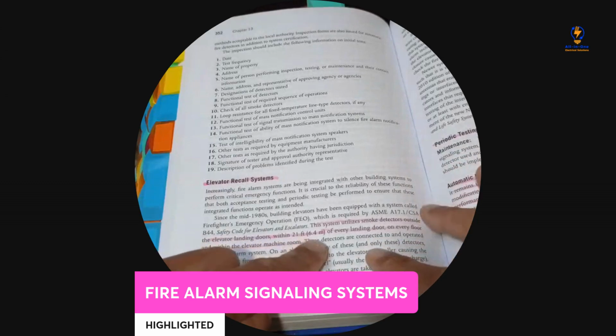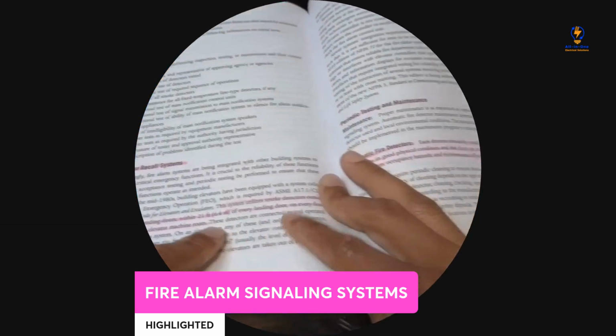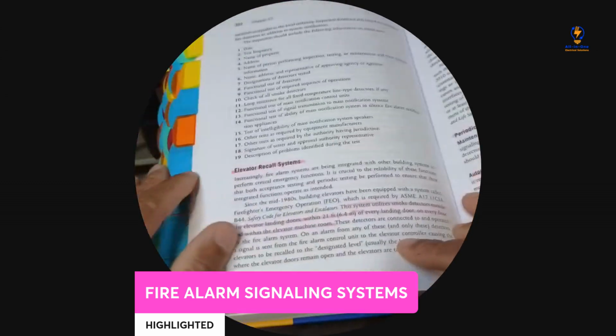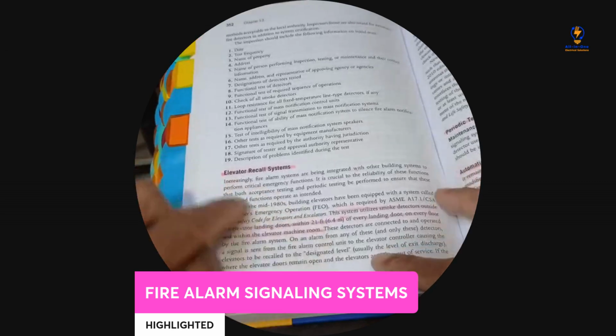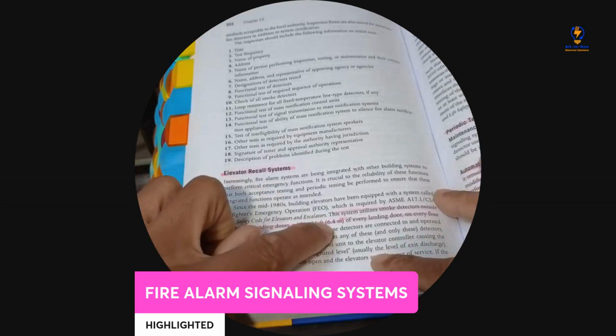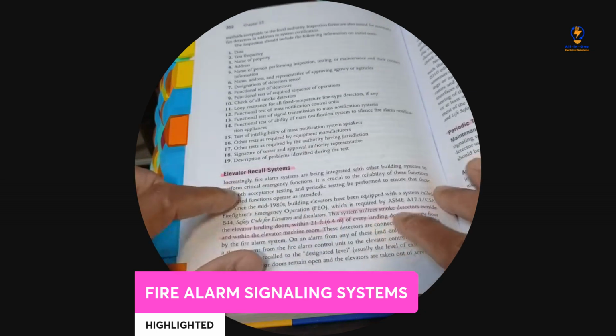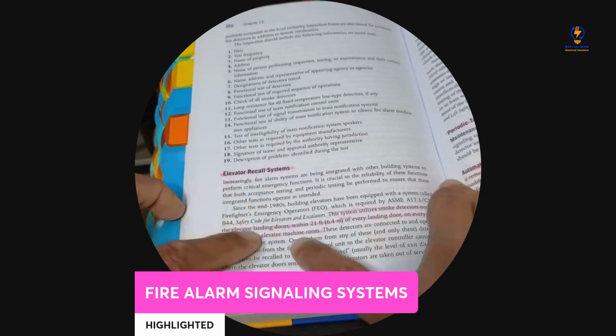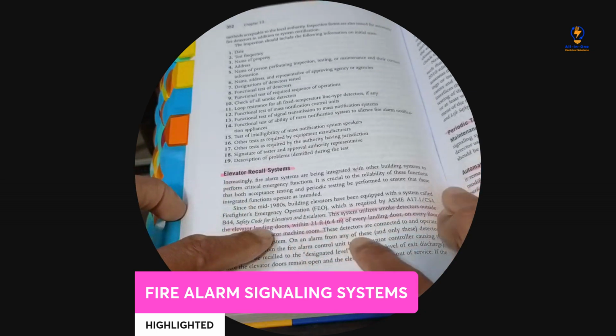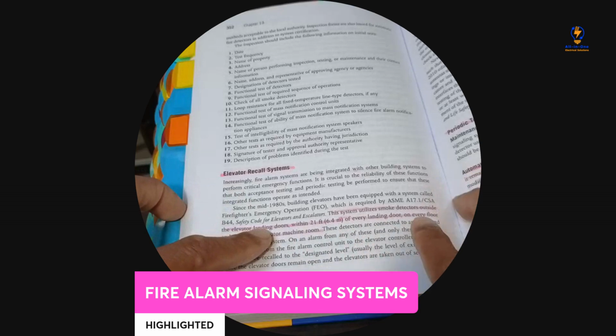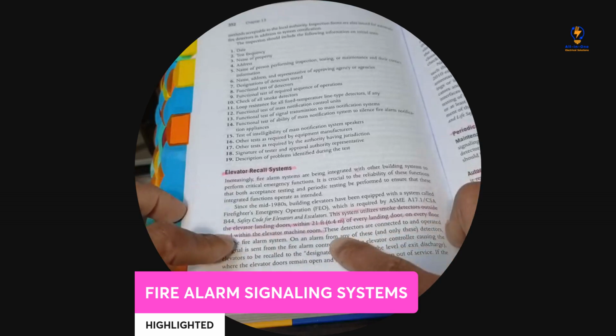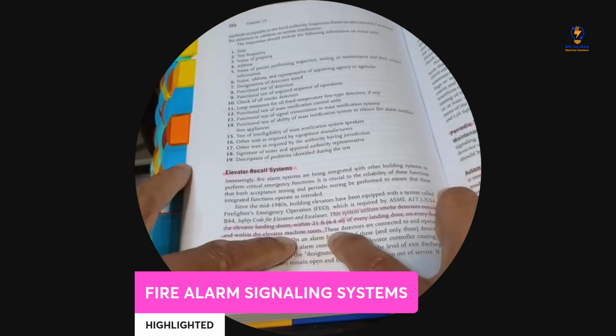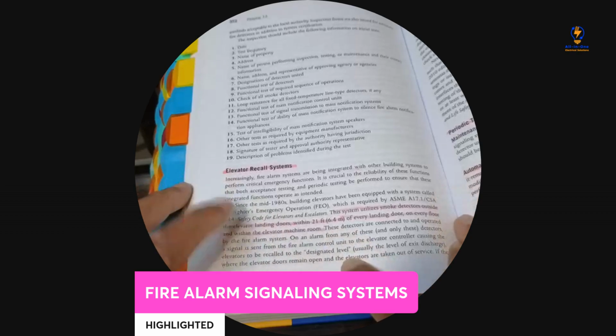You're going to go to here. Hold on, sorry. Second paragraph, middle of the second paragraph. These systems utilize smoke detectors outside of the elevators, landing doors within 21 feet of every landing door on every floor and within the elevator machine room. Very important, this one. Elevator recall systems.